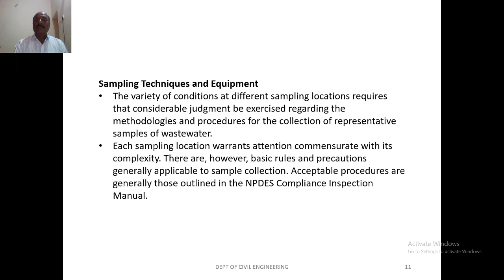Some important considerations for obtaining representative wastewater samples include: samples should be collected where the wastewater is well mixed. The samples should be collected near the center of the flow channel at approximately 40 to 60% of the water depth, where the turbulence is at maximum and the possibility of solid settling is minimized. Skimming the water surface or dragging the channel bottom should be avoided.